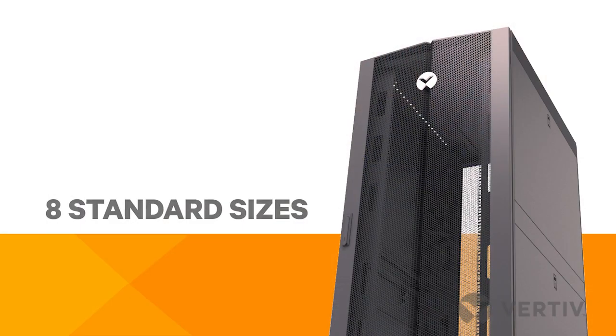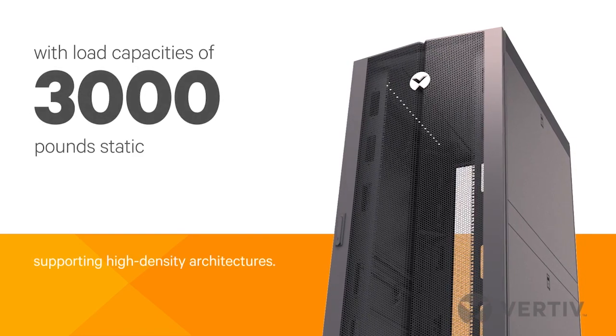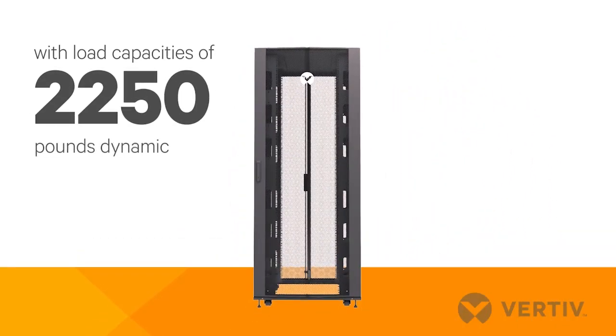Rich, are there any common mistakes end users make when purchasing a rack? Yeah, there are. Selecting the right rack from a weight load perspective, considering both the static and dynamic weight load limits, especially if customers are integrating off site, making sure that's in line with what you're deploying. We see that mistake happen, and it can have consequences you don't want to see. So that's an important one.